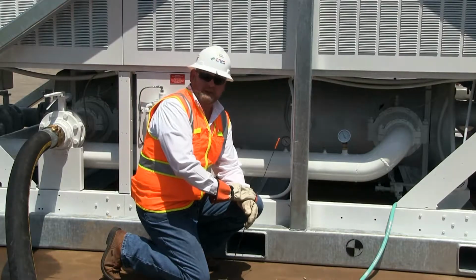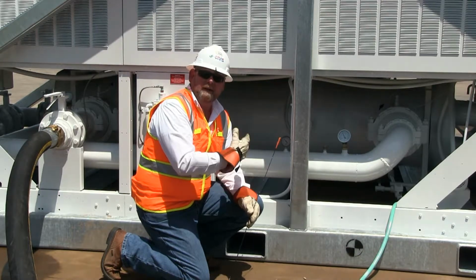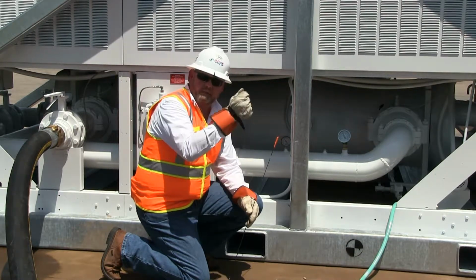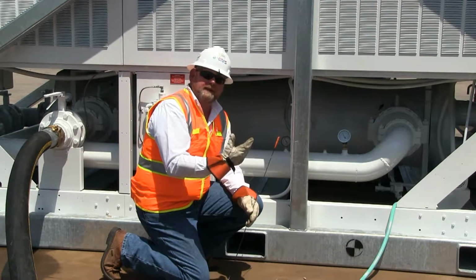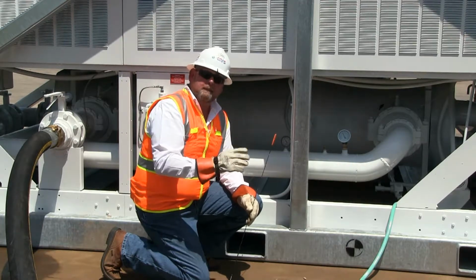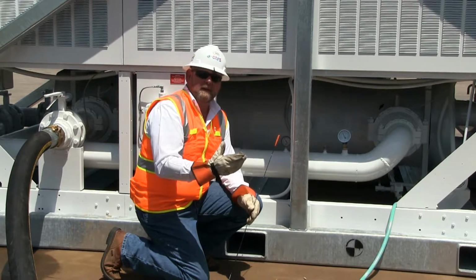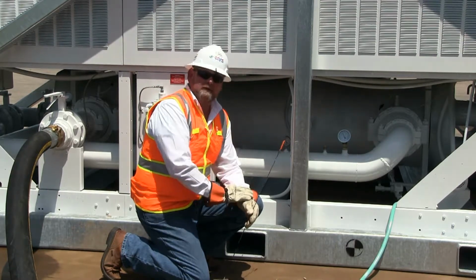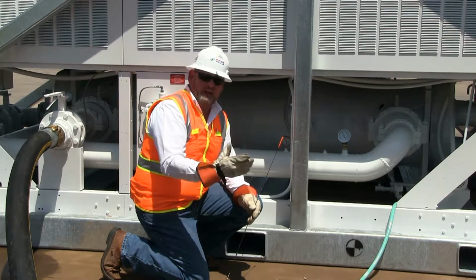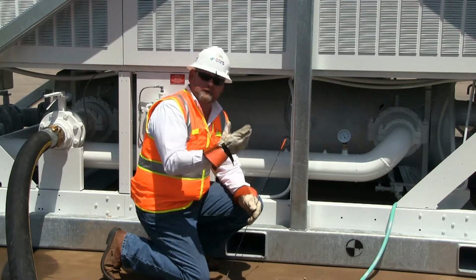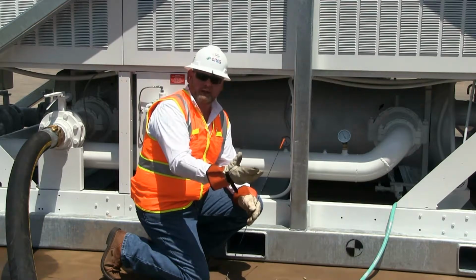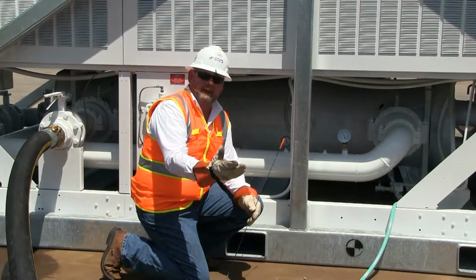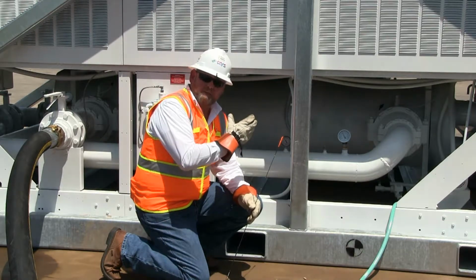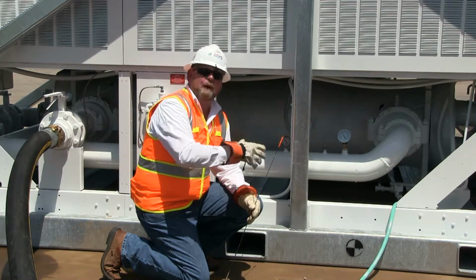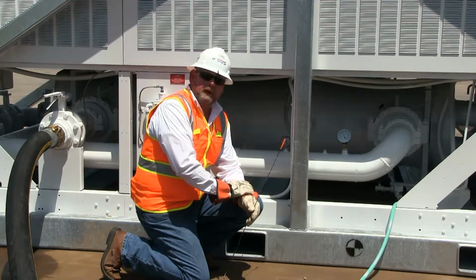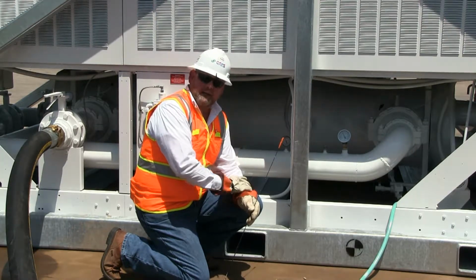Then your second high point is going to be your air unit if you're using one of the matching chilled water air handling units. There's an air vent at the top of those. You'll continue that process until you get all the air out of the system. Please note that if you don't have the air out of the system, you're not going to have the medium, the water, able to do your heat absorption and exchange through the chiller. The purpose of the chiller is to chill the water to circulate through the air handler or through the process application to gather heat, bring the heat back with the water to the chiller, where the chiller now removes that heat. So now that we're through that process, we're going to go up to the pump panel and show you how to get the pump started.